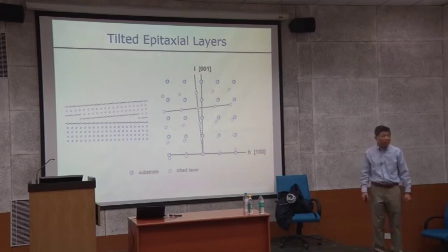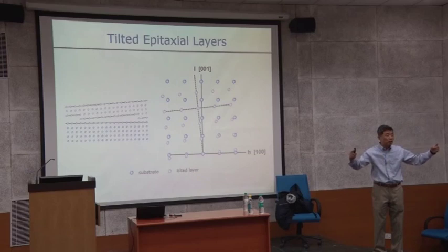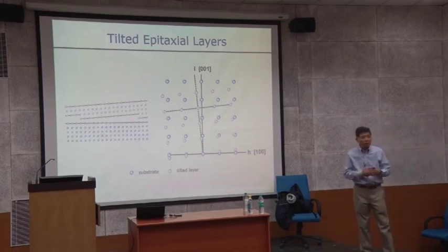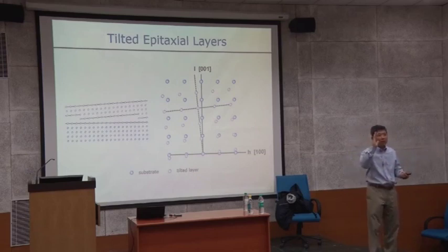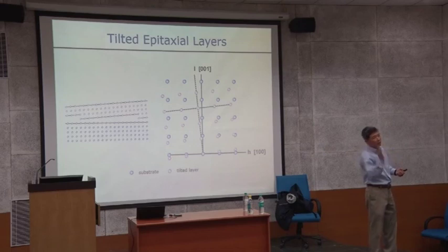Which one you pick, you get the best separation, strongest intensity reflection, and the best resolution. Usually your sample is facing here; I'll show the geometry later. You get a lower chi angle. Your resolution is better when chi is higher, close to 90 degrees.